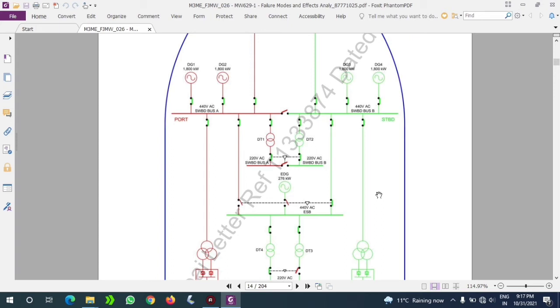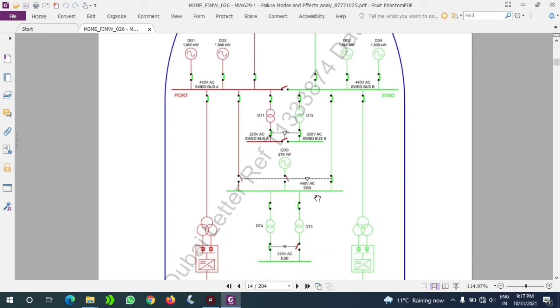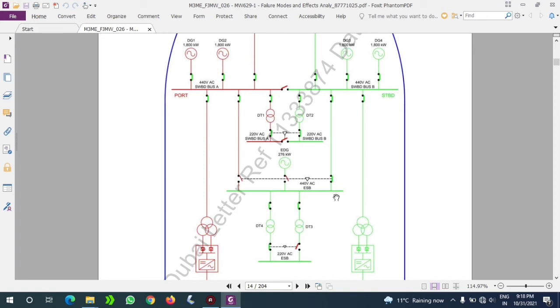You can easily see that again we have two transformers connected from emergency switchboard. Obviously, right now in this situation you can make out why we are using these transformers - yes, we are again stepping down 440 volt to 230 volt and giving this supply to the 230 volt emergency switchboard bus bar so we can give the emergency lighting supply to all the emergency lightings. For that we have two transformers, and again as I explained before there are input and output breakers for both transformers, primary side and secondary side.